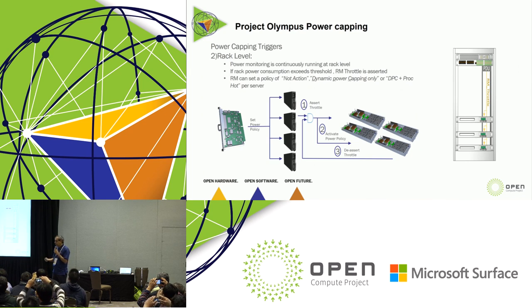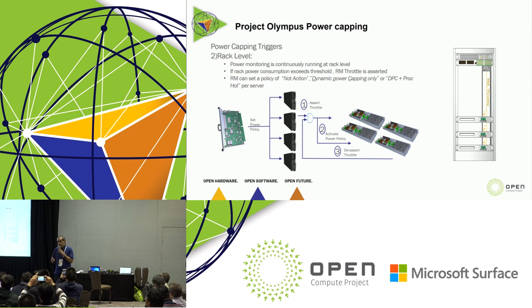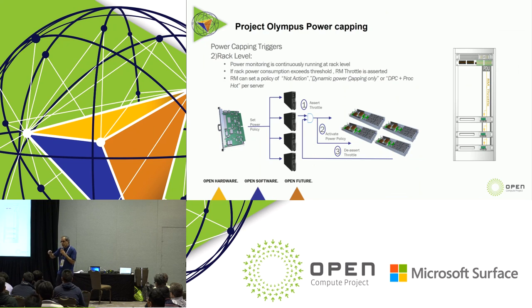At the rack level, we have a component called the universal power distribution unit. From the rack manager, to realize rack-level power capping, there is a signal called RM throttle running through the PDU that goes to every single server in the rack. That's used for the fast proc hot if needed — the first step of power capping goes to the lowest frequency possible, and then the policy is applied.